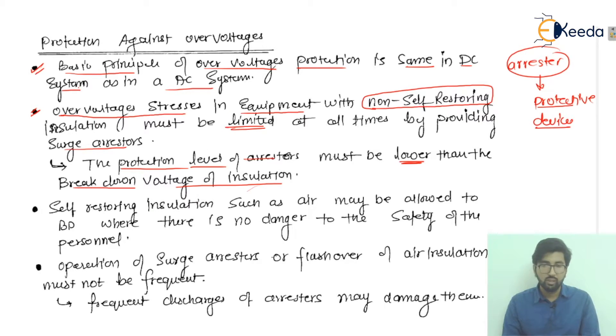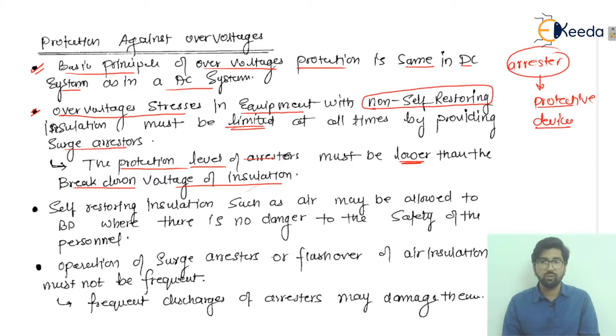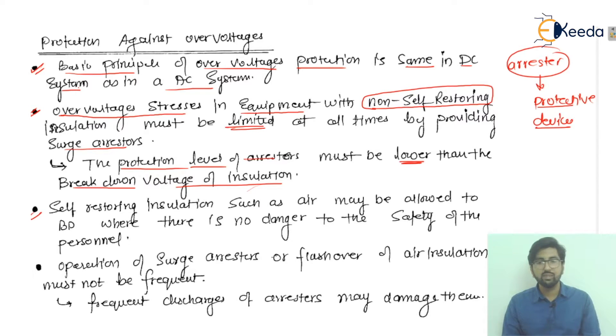The protection level of the arrestors must be lower than the breakdown voltage of the insulation. Self-restoring insulations such as air may be allowed to break down where there is no danger to the safety of personnel.